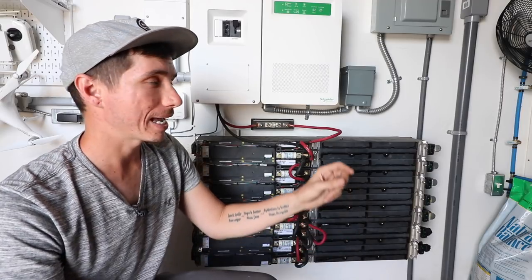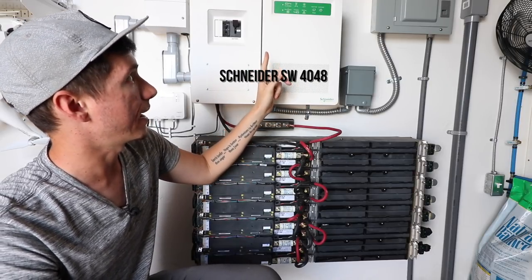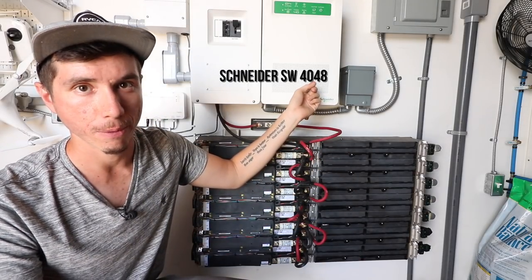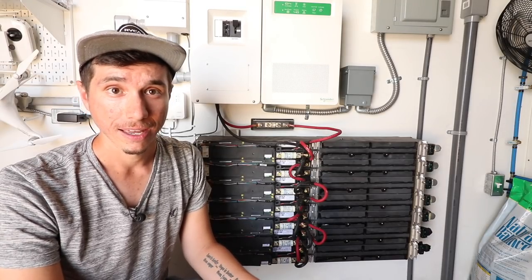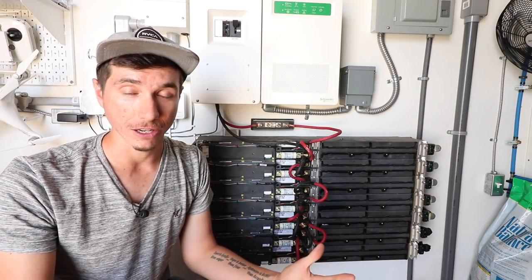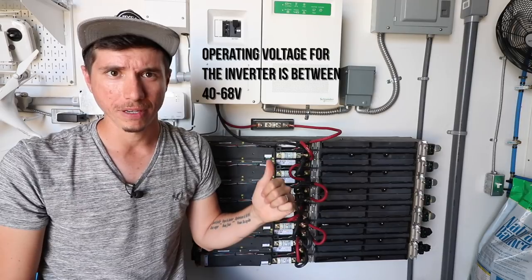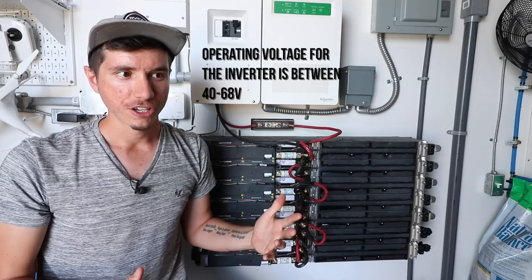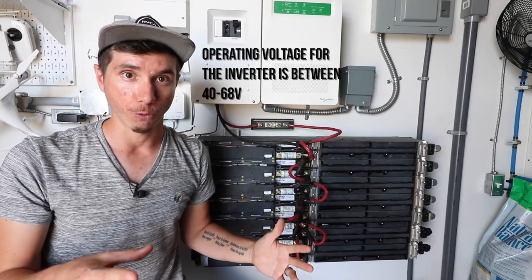The other major thing to check is the specs for the inverter. We're using the Schneider Conext SW 4048, which is designed for a nominal battery voltage of 48 volts. What's also really important is the operating voltage range of the inverter — you'll find this on the spec sheet. This inverter can handle up to 68 volts, with a minimum of around 40 volts, so the battery voltage must stay between 40 and 68 volts for it to work properly.